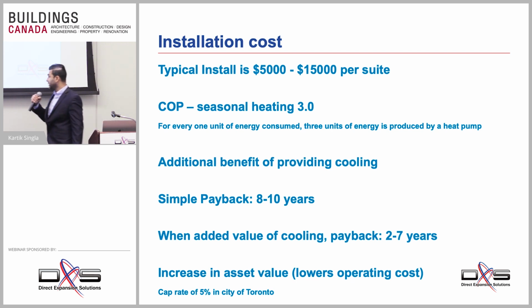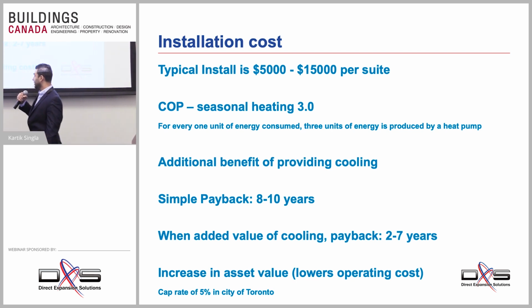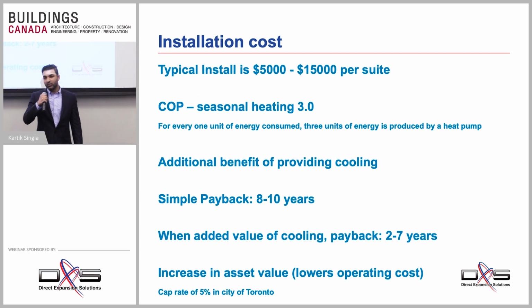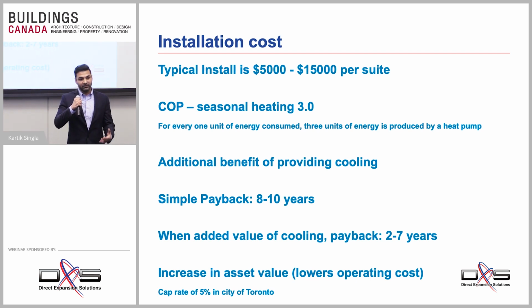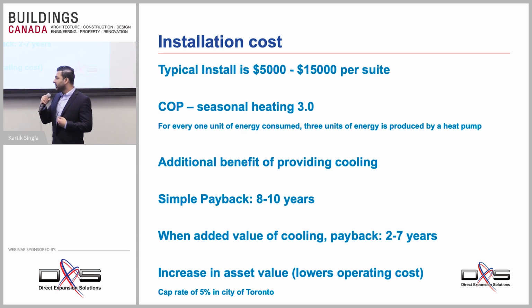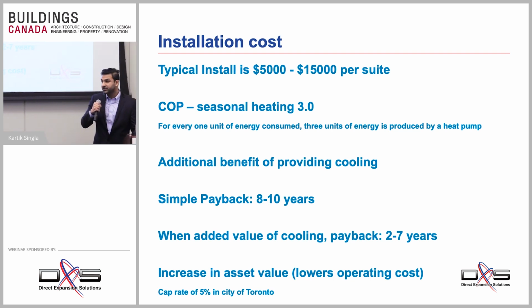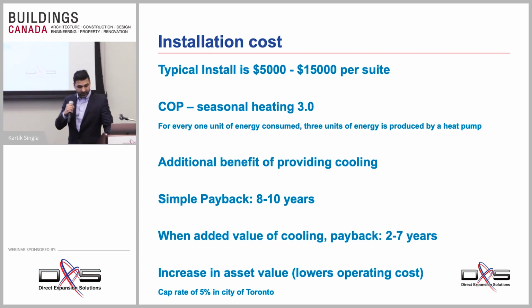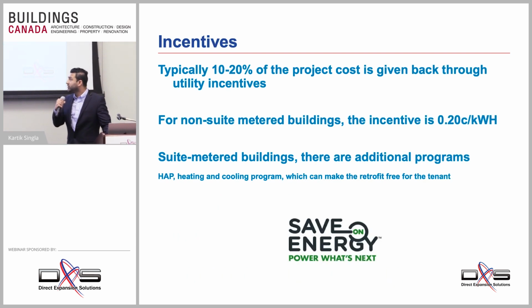And actually, the last point I wanted to mention is that with VRV systems, you are reducing the operating cost of your asset, of your building, which increases the asset value. So if you take the cap rate of 5% into consideration, which is typical for City of Toronto, essentially you're reducing your operating cost by a certain amount every month. You can see returns on the value of your asset instantaneously, and I'd be happy to talk more about that if there are questions.